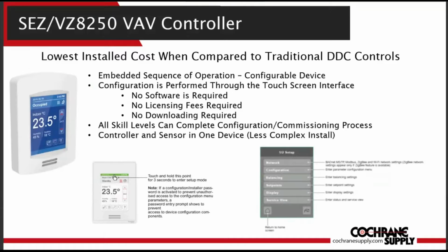Accessing the configuration pages is done by pressing the top portion of the touchscreen. This will take the user to 2 pages of setup that includes configuring the operation of the device, network settings if connected to a network, configuring the set points, configuring the display, setting the time clock and schedule, associating the wireless sensors, as well as commissioning operations.